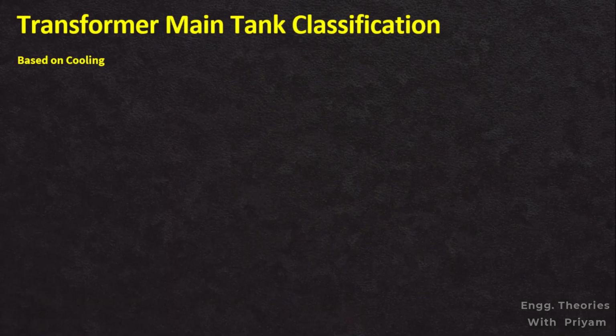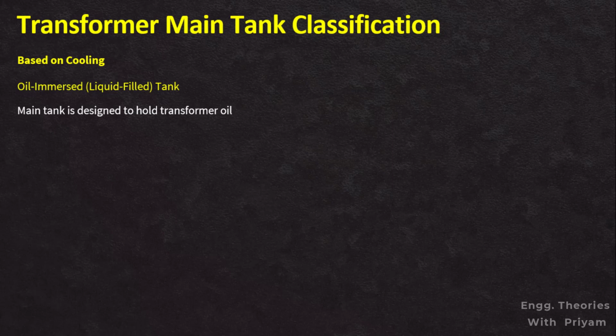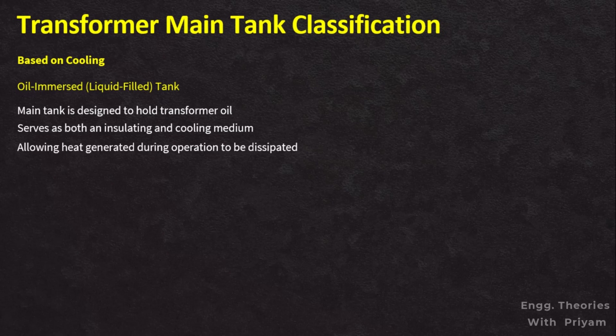Cooling. Based on cooling, the main tank of the transformer can be classified into different types. First type is the oil immersed or liquid filled tank. In oil immersed transformers, the main tank is designed to hold transformer oil, which serves as both insulating and cooling medium. The core and the windings are immersed in the transformer oil, allowing the heat generated during operation to be dissipated through the oil to the tank walls and surrounding air. Oil immersed tanks are commonly used in medium and high power transformers due to their efficient cooling capabilities.